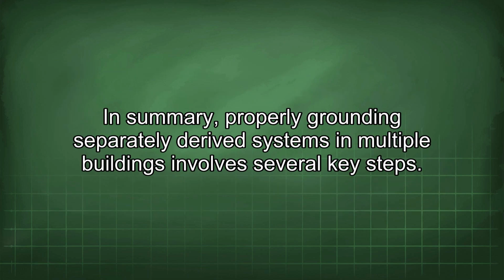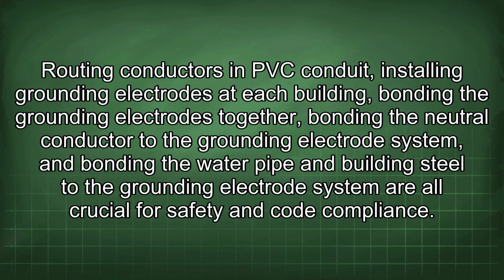In summary, properly grounding separately derived systems in multiple buildings involves several key steps: routing conductors in PVC conduit, installing grounding electrodes at each building, bonding the grounding electrodes together, bonding the neutral conductor to the grounding electrode system, and bonding the water pipe and building steel to the grounding electrode system. These are all crucial for safety and code compliance.